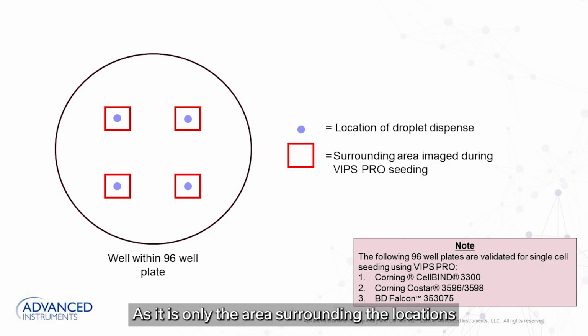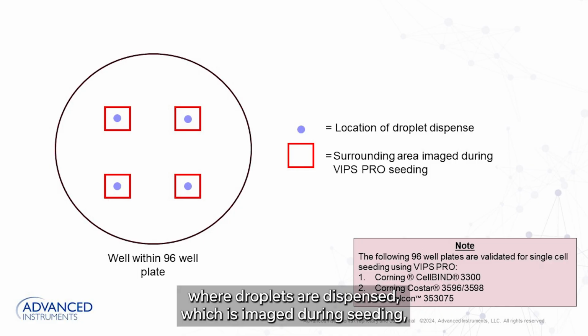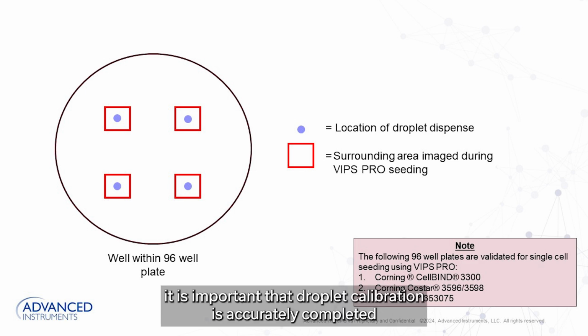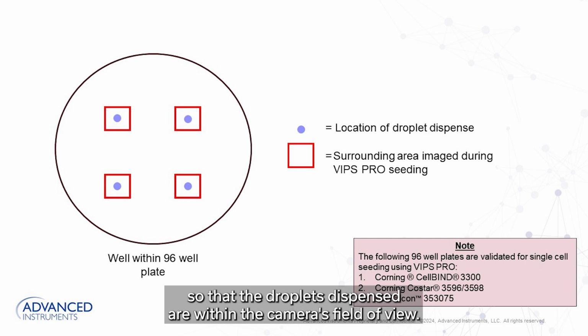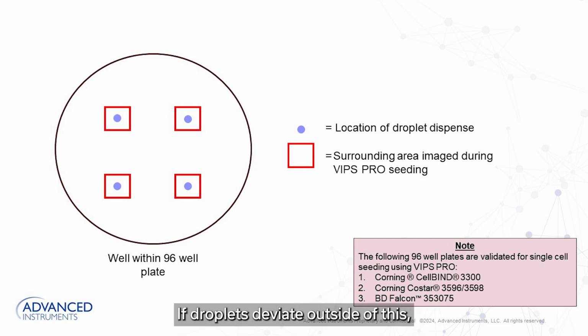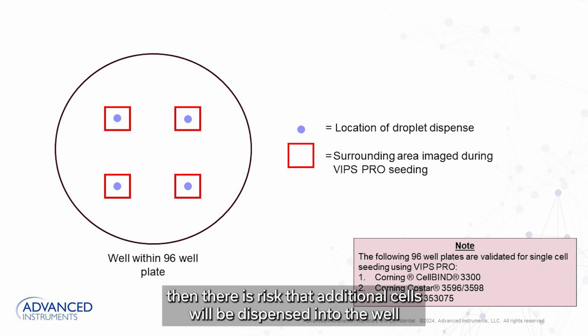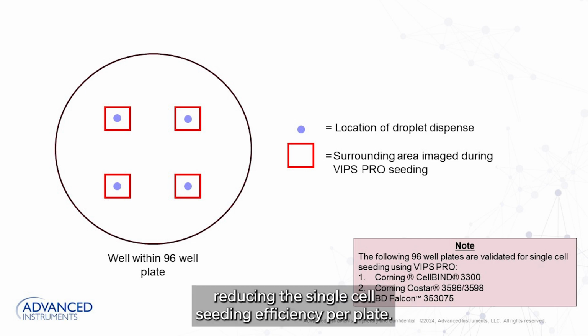As it is only the area surrounding the locations where droplets are dispensed which is imaged during seeding, it is important that droplet calibration is accurately completed so that the droplets dispensed are within the camera's field of view. If droplets deviate outside of this, then there is risk that additional cells will be dispensed into the well, reducing the single cell seeding efficiency per plate.